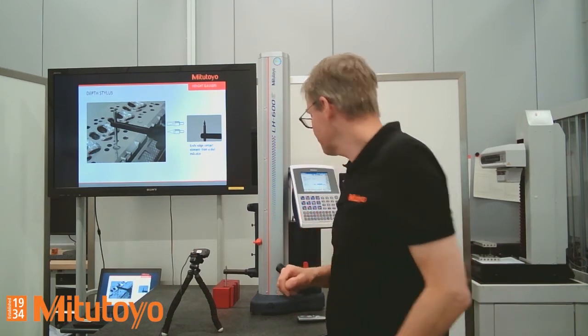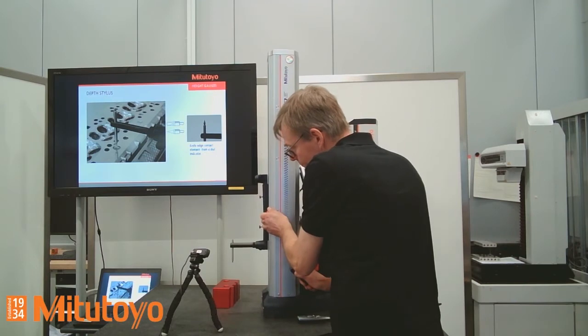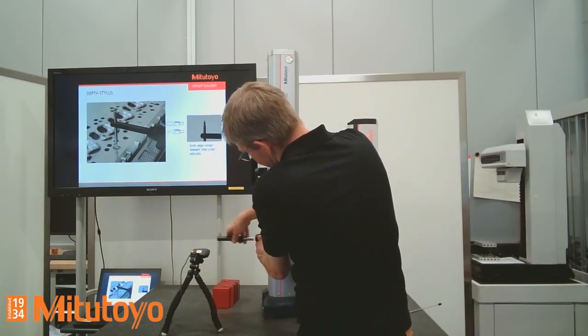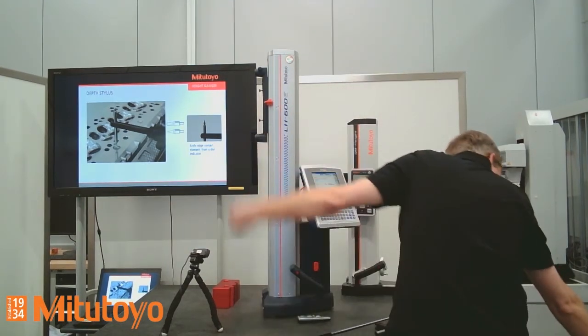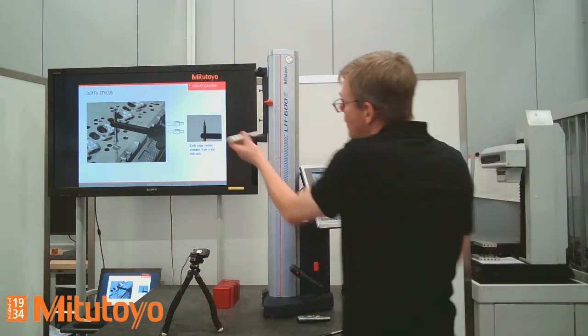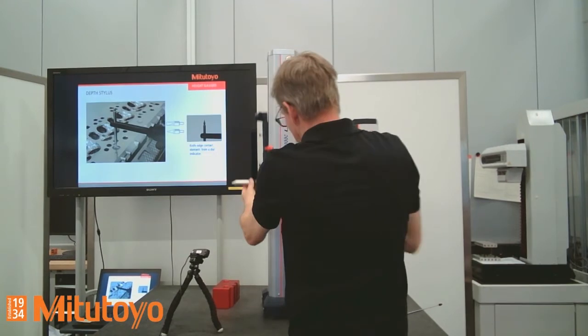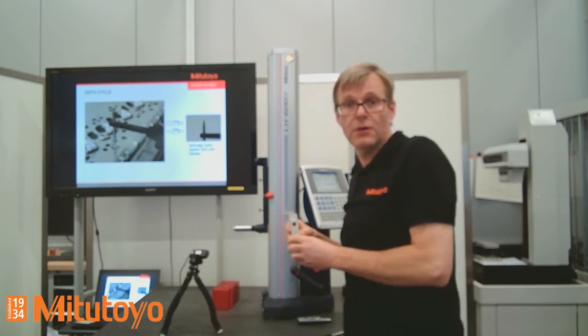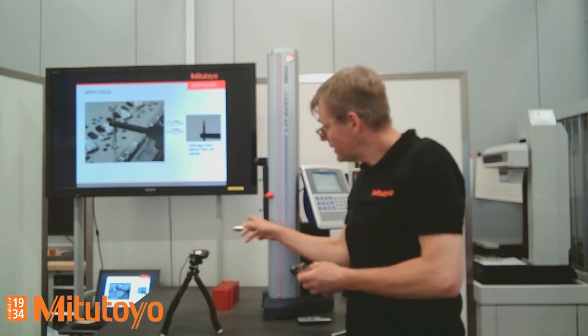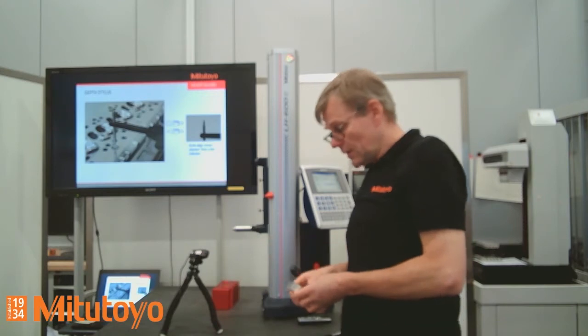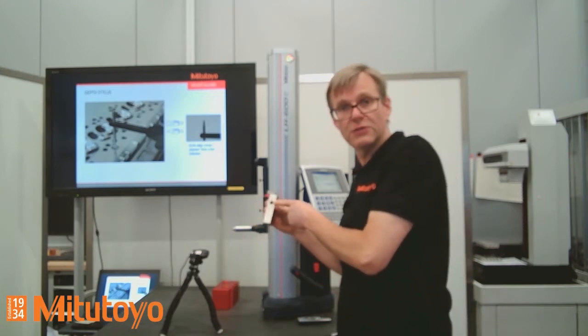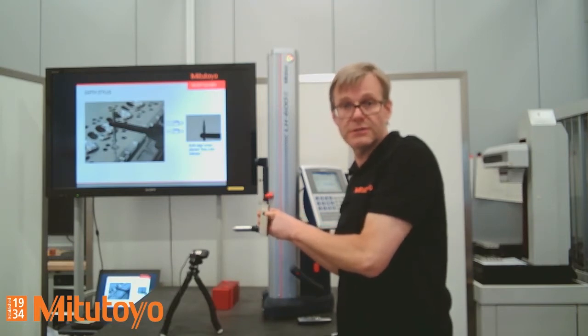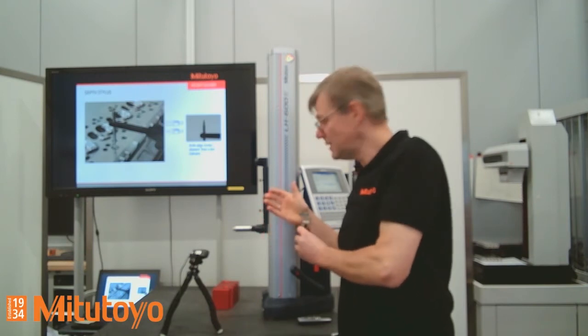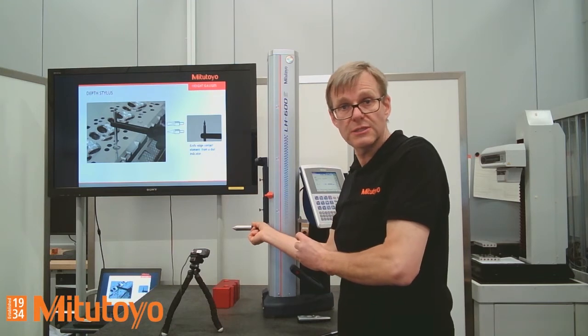So the next one is a tapered probe. So again, I have to change the probe. So for the tapered probe, I need another reference setting block because I need the offset of this one here to the granite plate. So you can see here, there is a special hole integrated in the setting block and there is a value written on the setting block. So, and based on this value, I can put in the offset of this tapered probe into the controller box. This is important to do.